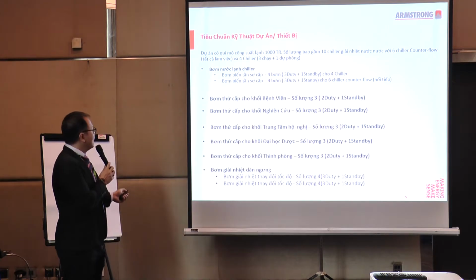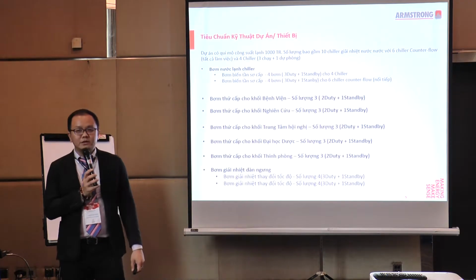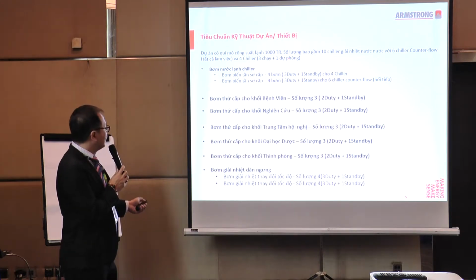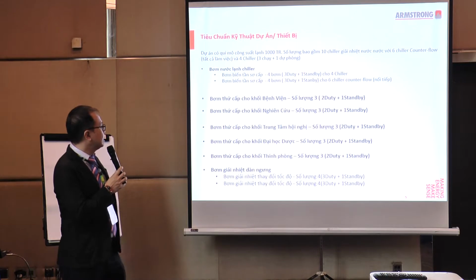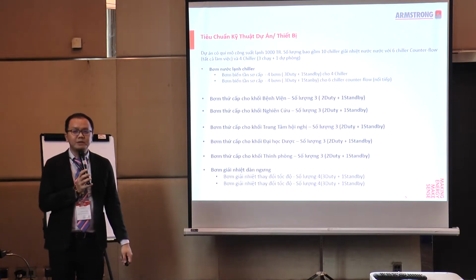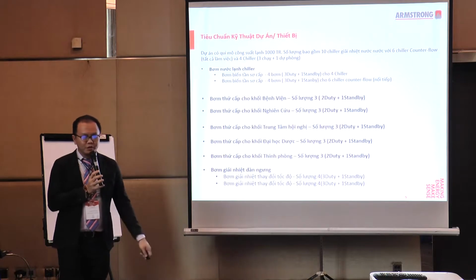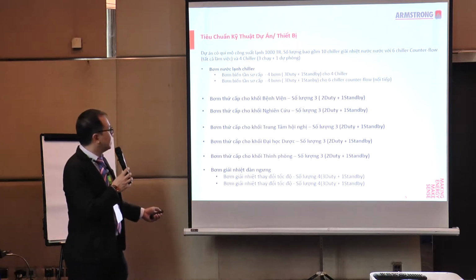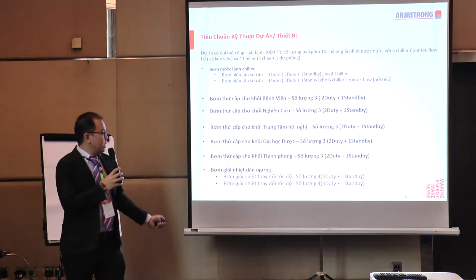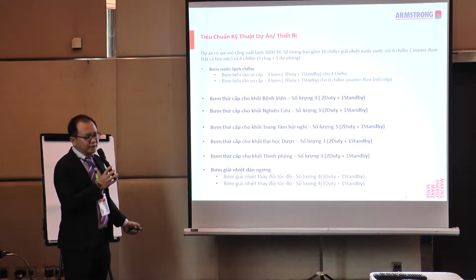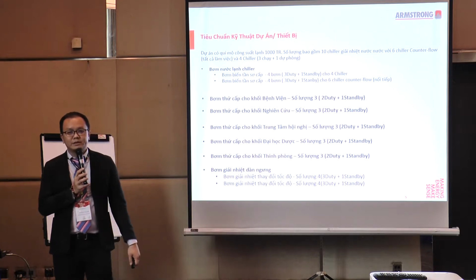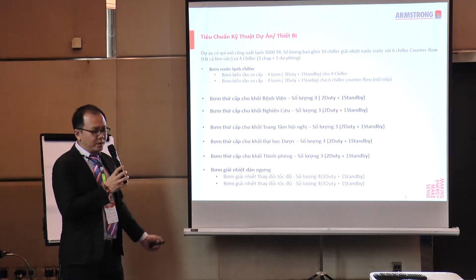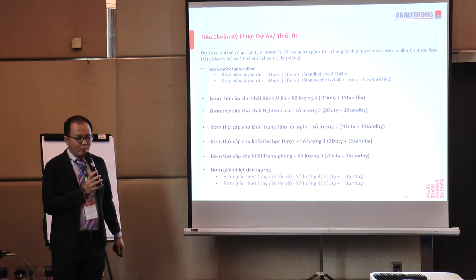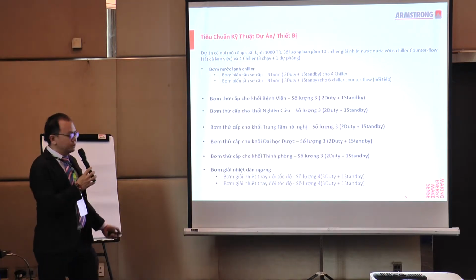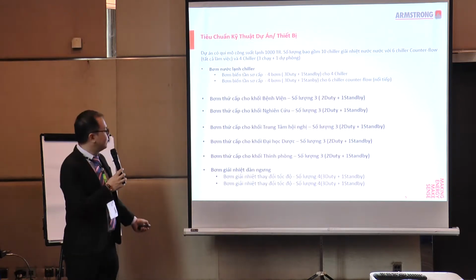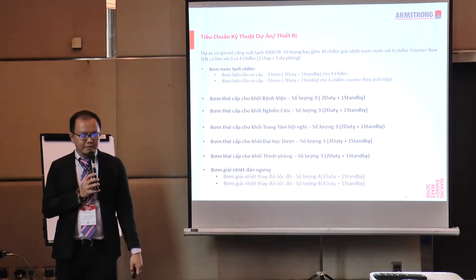In terms of the specifications of the primary and secondary pumps for all the 5 blocks, we started off with the 10 chillers with variable speed primary pumps designed for the 4 chillers, and also the 6 remaining for the counterflow. For the other 5 blocks of buildings, the hospital, research, convention center, medical college, and auditorium, we have the remaining 2 duty and 1 standby pumps. We also have the condenser pumps, which are 4 with 3 duty and 1 standby.